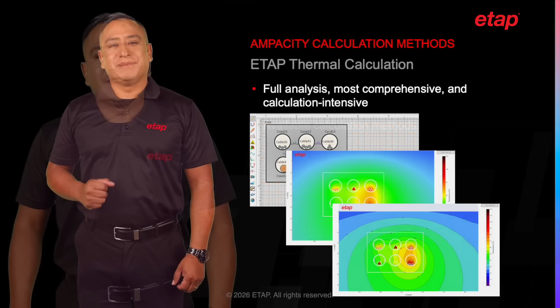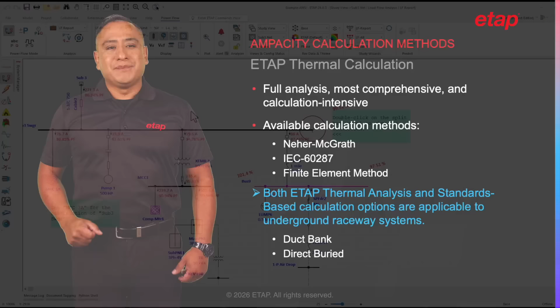In ETAP, the available thermal calculation methods for thermal analysis include the Neher-McGrath method, the calculation method provided in the IEC 60287 standard, and the finite element method, which handles more complex scenarios, incorporating a flexible and detailed approach. In ETAP, both the thermal analysis calculation method and the standards-based option are applicable to underground duct banks and direct buried cable installations. Let's go over the features in ETAP and then demonstrate an example.